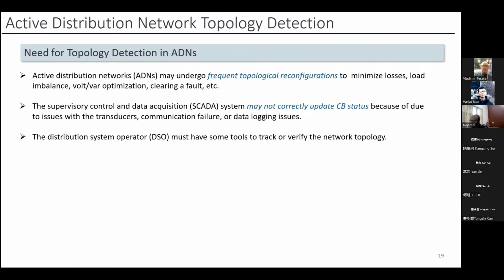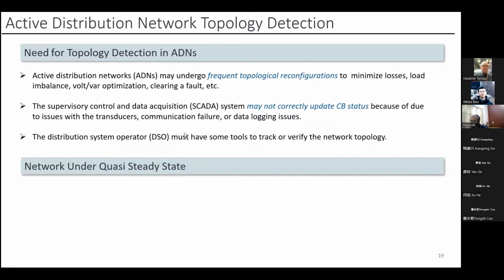However, due to communication issues and data updation issues, sometimes the CB status is not correctly reflected in the SCADA system. This has been observed in various practical scenarios, so the SCADA system may not log the right circuit breaker status. As a result, the topology of the network is not correctly estimated, and all processes depending on this topology information, such as state estimation, will not give good results if we don't have the right topological information of the network. So how do we address this issue of CB status being incorrectly reflected in the SCADA system?